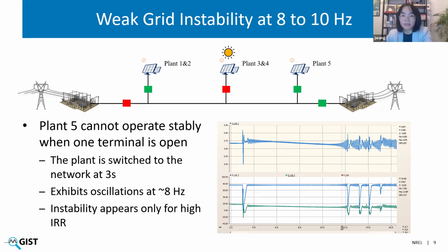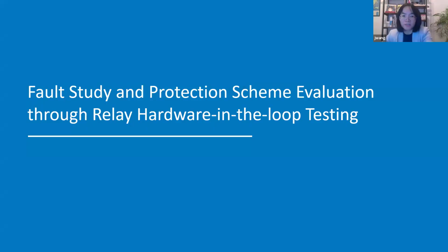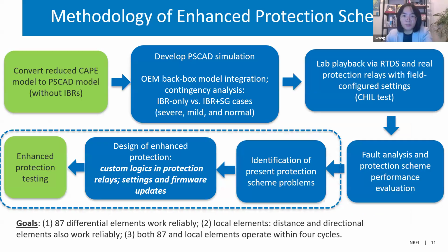So those are just some example results of the model validation and the stability analysis. Now I'm going to move to the fault study and the protection evaluation. So this slide shows the methodology. So how do we do it? We first convert the reduced CAPE model to PSCAD. We don't have a good grid forming model for the CAPE software, so we have to do it in PSCAD, and so we first do the PSCAD model.